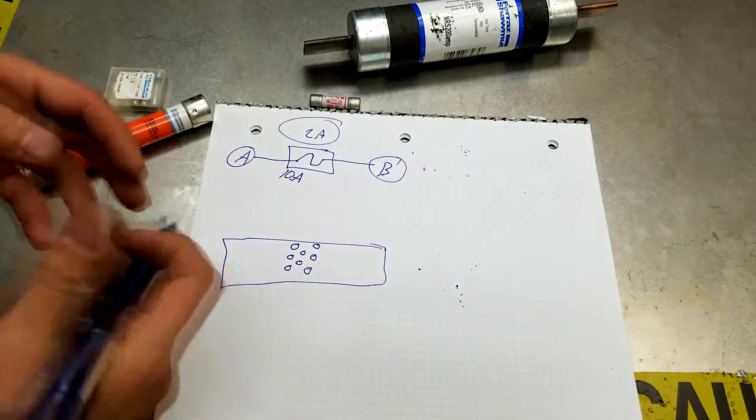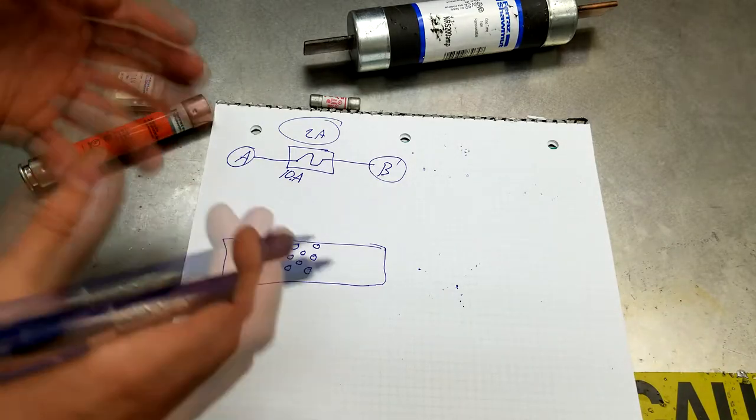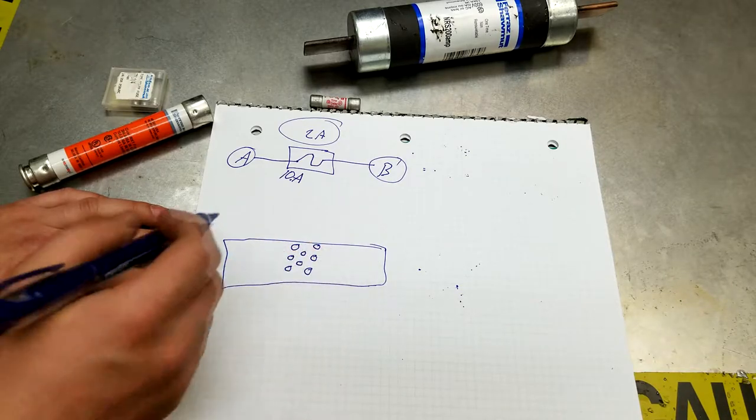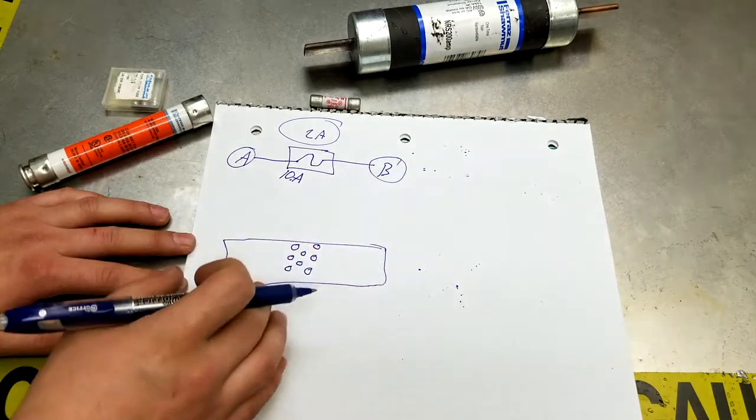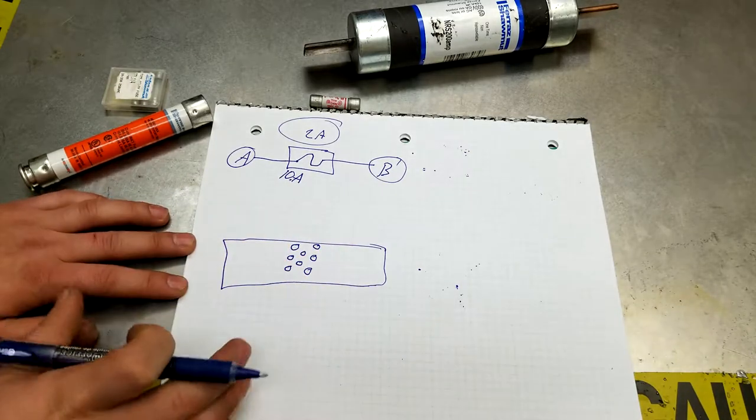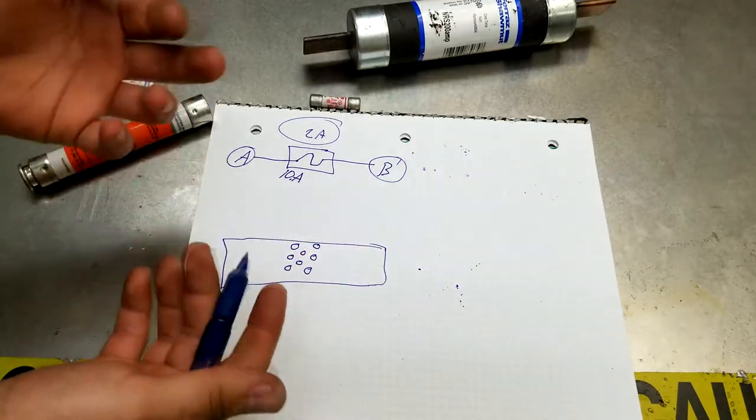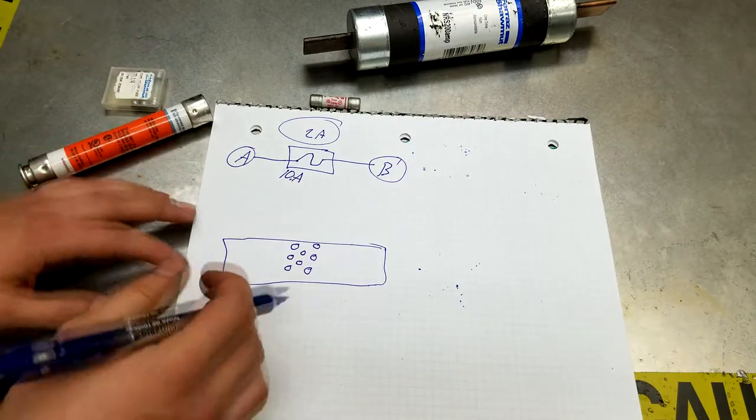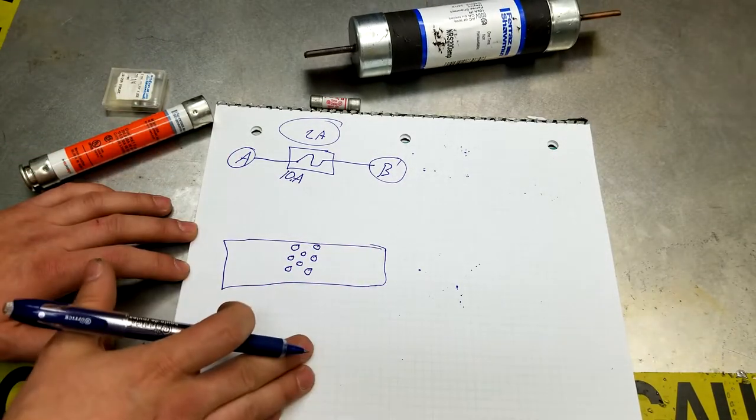But when it heats up, when the current exceeds, the current can exceed the rating of the fuse for some time. Let's say it's powering your motor. So when the motor starts, it will be pulling, for example, five times more current than it's rated for. So this will allow for that. It will heat up, but it will not blow, because it's designed to pass a certain current through for some time. But when it heats up, it will start melting, and when it melts it will open, therefore disconnecting the power.